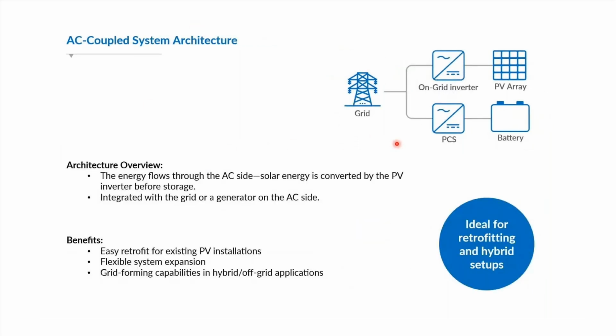For an AC coupled energy storage system, the solar energy generated by the panel is first converted into AC by a dedicated PV inverter, or on-grid or off-grid inverter, whatever it is. That AC power then either supplies your active loads directly or flows through a power conversion unit, often called a PCS or inverter charger, to charge the batteries. What's important here is the use of a shared AC bus - all components, the grid, generator, loads, and battery storage, are connected and talking at this AC level provided in AC coupled systems.